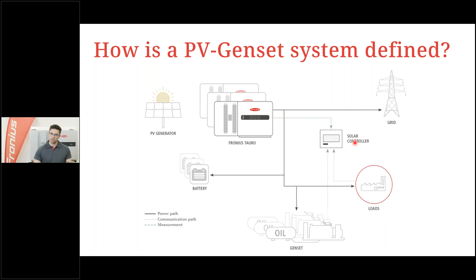So we have heard the main task of the PV Genset controller is to protect the diesel generator and to regulate the output power. We see here a schematic, and it basically shows us a load curve. This would be this gray area. And the energy under this load curve will be provided by the genset. Now, if we have solar as well, during the sun hours we produce a lot of green energy and support the diesel generator. And this will be relieved by the dark gray area. So this will be the part that is provided by the Fronius inverters.